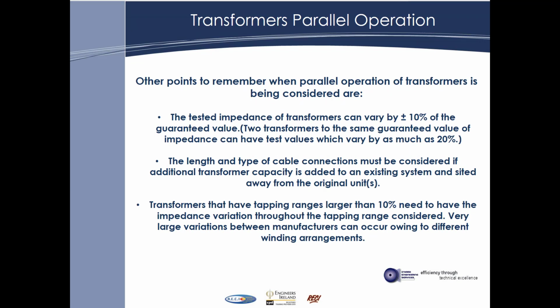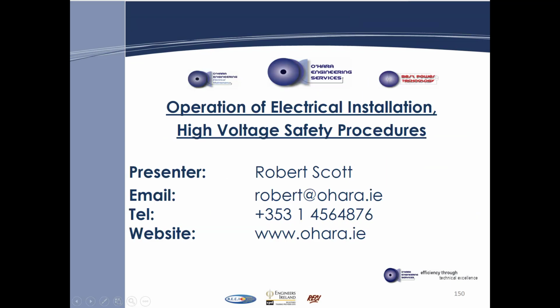The other point to remember when paralleling transformers is that the testing impedance of the two transformers can vary by 10% of the guaranteed value. Two transformers of the same guaranteed value impedance can have test values which can vary as much as 20%. The length and type of cable connection must be considered if additional transformer capacity is added to the existing system and sited away from the original unit. Transformers that have tapping ranges larger than 10% need to have the impedance variation through the tapping range considered. Very large variations between the manufacturers can occur owing to different winding arrangements.